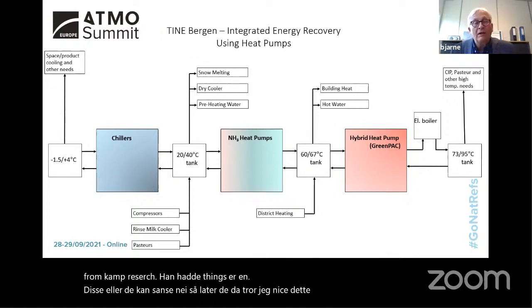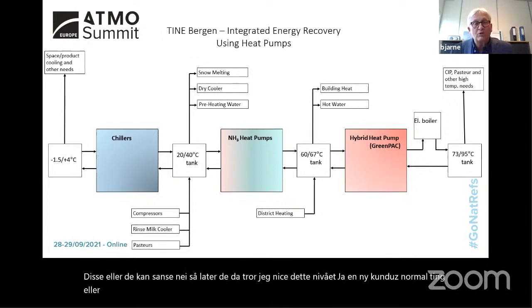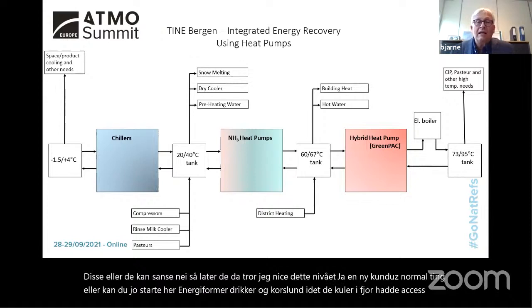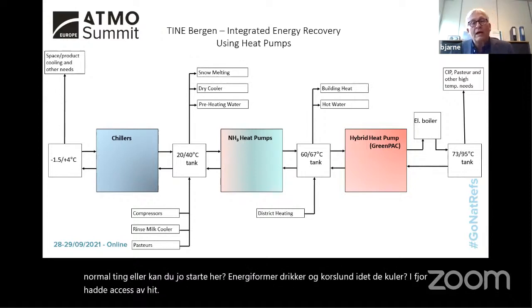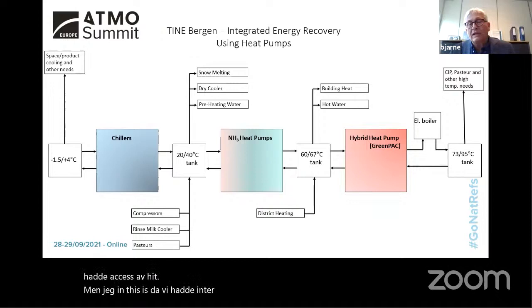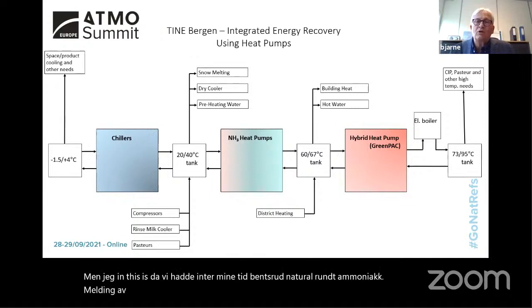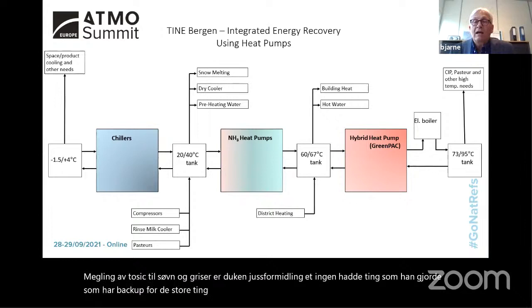You can do snow melting, and use the energy from the dry cooler - of course you need a dry cooler if you have excess heat. In this system, we have intermediate heat pumps with natural refrigerant ammonia, making up to 67 degrees that you can use for building heating and other things. You also have a backup for district heating to this tank.